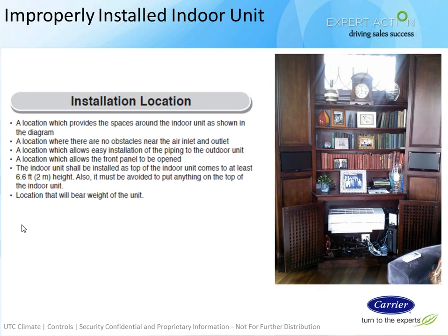Installation of the indoor units. Allow proper clearance. You should allow about 6 inches all the way around the unit to provide proper airflow on the supply side and the return side. These units have louvers on the bottom, and that's where the air comes out, of course, but they also return on the top. So you have to have unobstructed clearance on the top to get to those return air grills that you see there on the top of this cabinet.